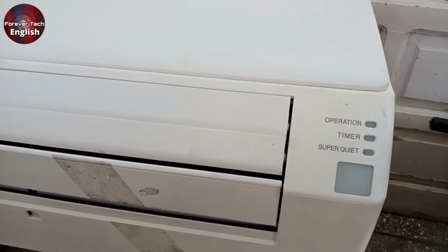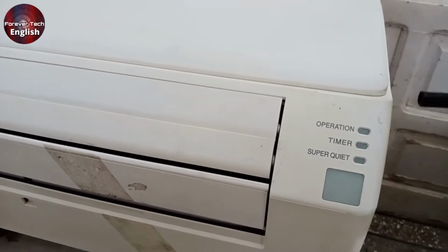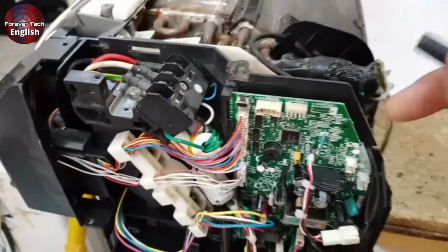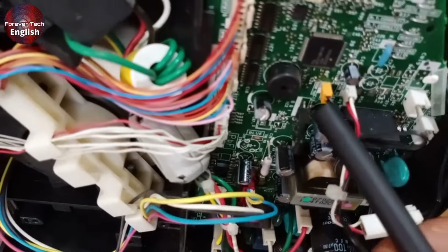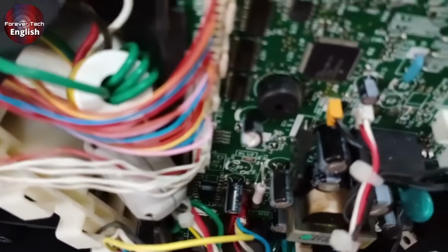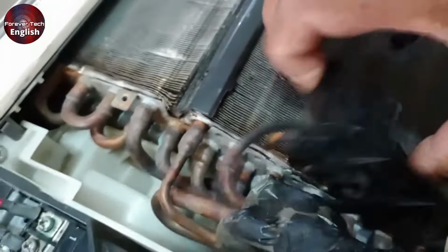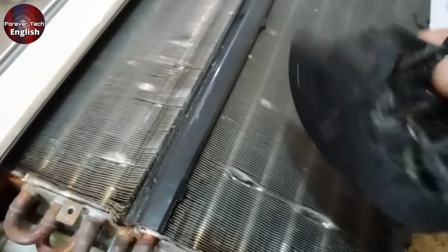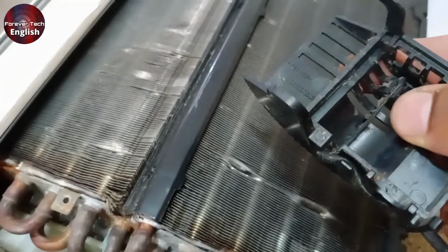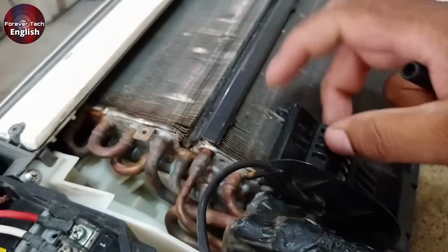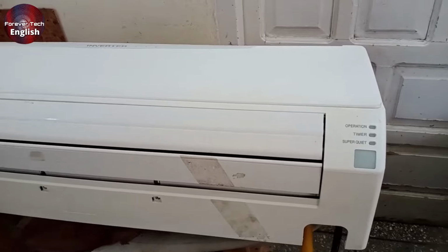Let me show you where the room temperature sensor is located inside the indoor unit and on the PCB. Here is the indoor PCB, and as you can see, there is a yellow connector with a black wire. That's where the room temperature sensor is connected. It is mounted in the coil area, and if you look here, you will see it fixed in this spot. Once you change it, the error, 2 operation blinks plus 2 timer blinks, will be cleared and your unit will return to working condition. Now, let's discuss the next error.